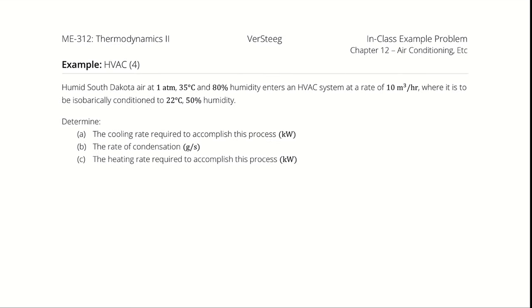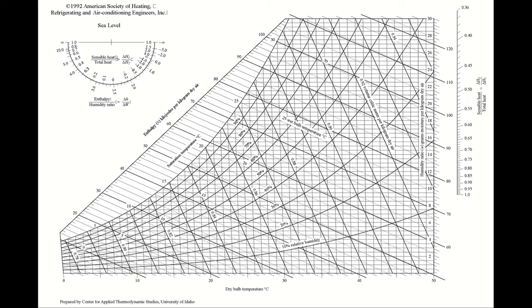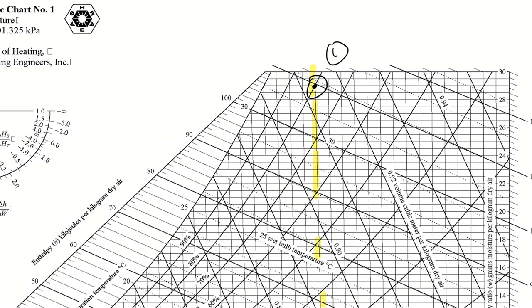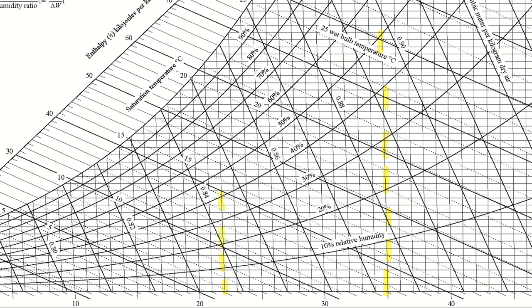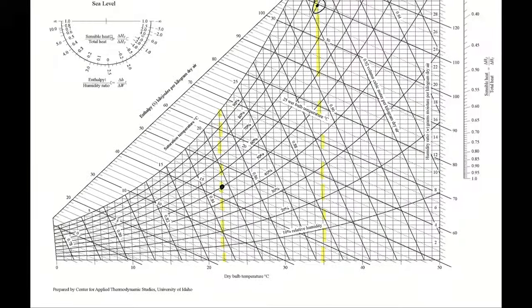Let's start by visualizing this on the psychrometric chart. We are starting with 35 degrees Celsius and 80% humidity. 35 degrees Celsius and 80% humidity is going to be right here — I'll highlight that number. That's state 1. And we are trying to get down to 22 degrees Celsius and 50% relative humidity. Our end condition is right here. I should call that state 3.